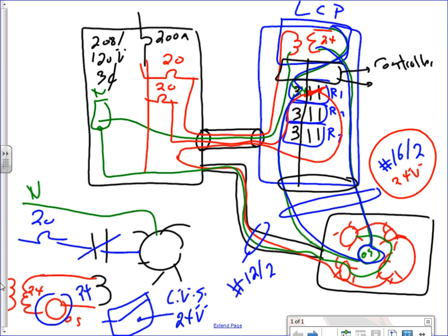There's also a timer function inside the relay coil control. You can put a timer on that coil and control it by schedule. Most lighting control panels have a sweep function: at around 10:30 at night, the panel sends a signal to every relay — bang bang bang — opens them all at 10:30. That's called sweeping the lights off to save energy when everyone has gone home.